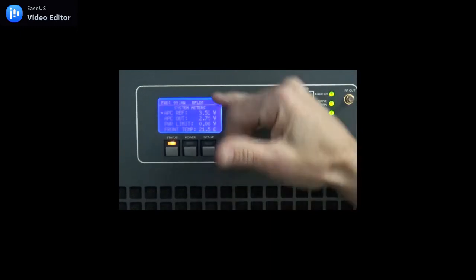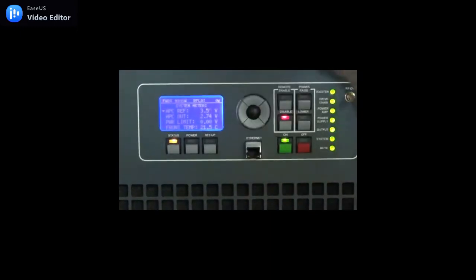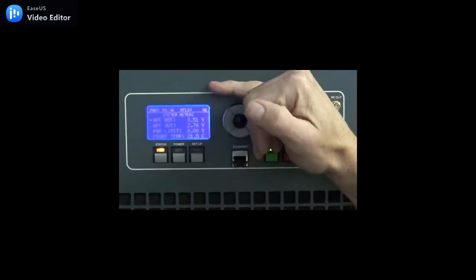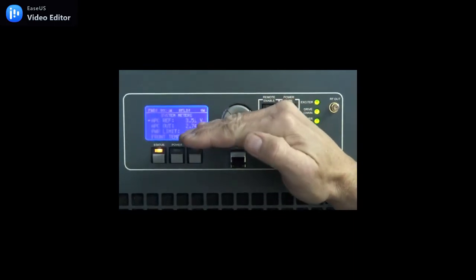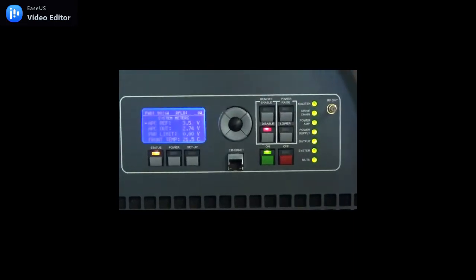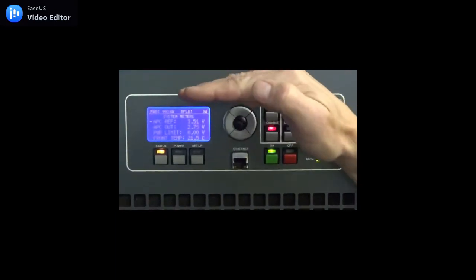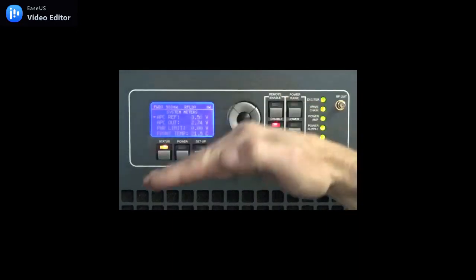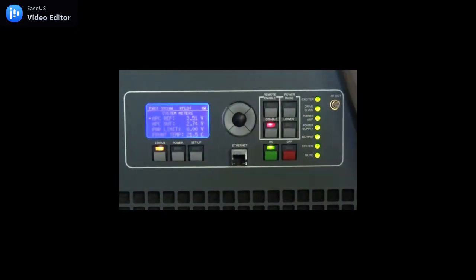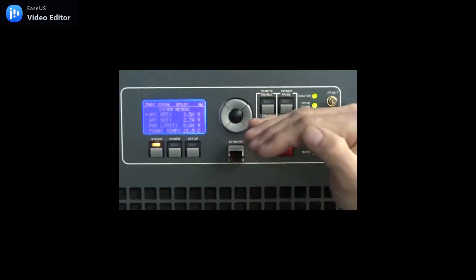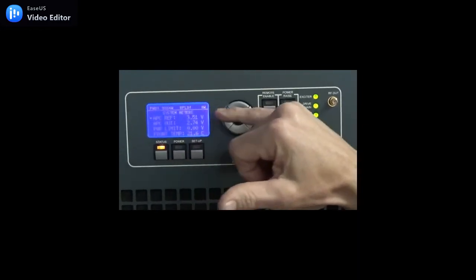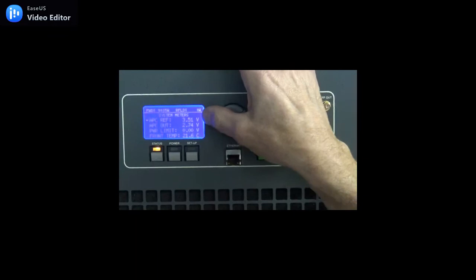So what we're going to do is watch this APC voltage as we adjust our APC limit. Once we hit that threshold, you'll see the power will start to decrease, so that will force this APC up. At that point, that is kind of our limit right there of the APC. That's the threshold of the APC. So once we hit that knee, we're going to go back up and raise that up off that knee by about 300 counts, and that's where we'll leave it. So to start with, we got about 2.74 volts. That's where you're normally going to be sitting after the power cal. Your APC reference is always going to be 3.5. So we've got a good power cal. So now we're ready to set that limit.